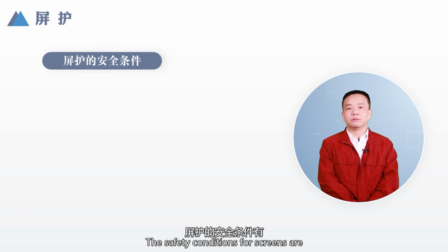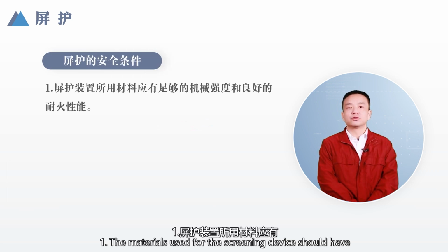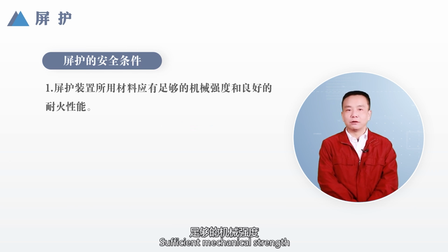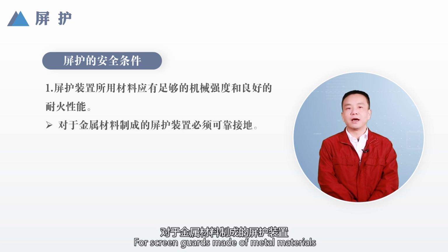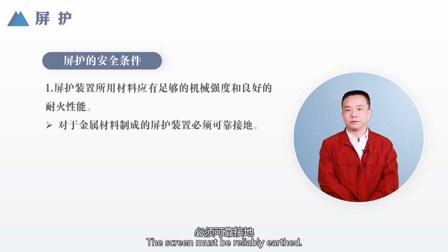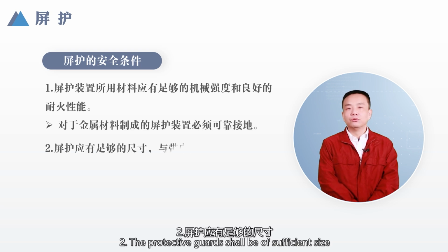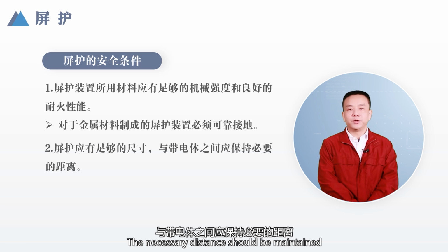The safety conditions for screens are: 1. The materials used for the screening device should have sufficient mechanical strength and good fire resistance. For screen guards made of metal materials, the screen must be reliably earthed. 2. The protective guards shall be of sufficient size. The necessary distance should be maintained between the screen and the electrically energized body.